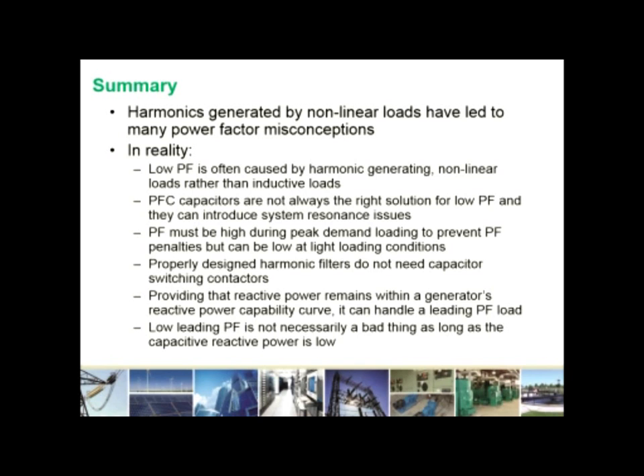Providing that reactive power remains within a generator's reactive power capability curve, it can handle a leading power factor load. And low leading power factor is not necessarily a bad thing, as long as the capacitive reactive power is kept low.